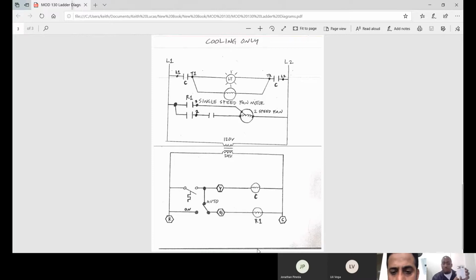If you switch it to on, the fan is just going to come on and run regardless of whether you're using the heat or the AC at all. So you could have the AC and heat off, not use either, and just flip that on and run the fan to circulate some air. This is operated by the G circuit. So G is your fan circuit, Y is your cooling.